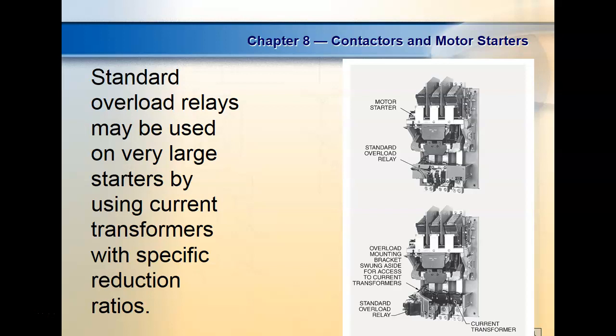Everybody got that? You don't measure current, you measure what? What can you do if your ammeter can't read it? I learned this little trick too. If the current was so low on the wire, we looped the wire through the transformer several times. I've seen that trick a lot. With the ammeter, if they can't get a good measurement, they loop through there and then just divide it out.